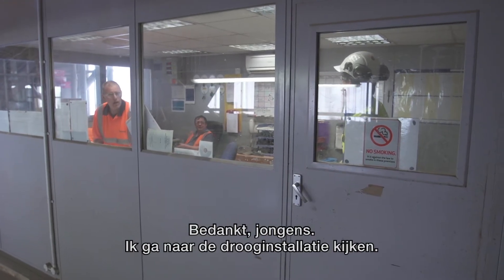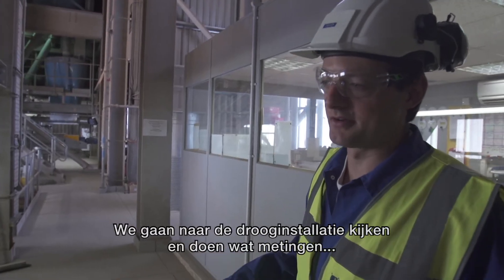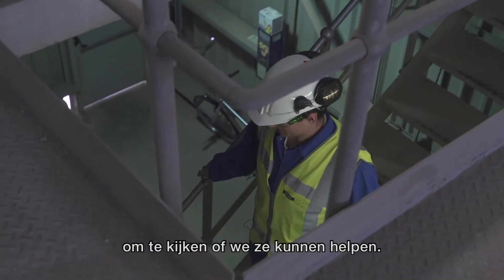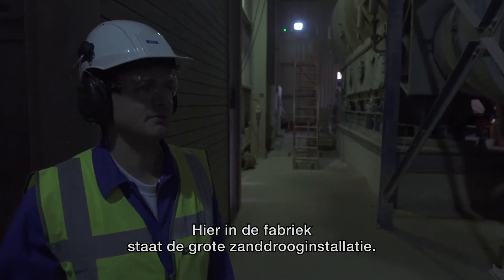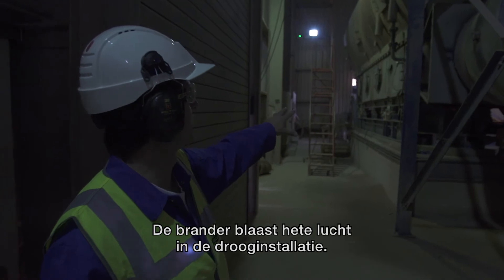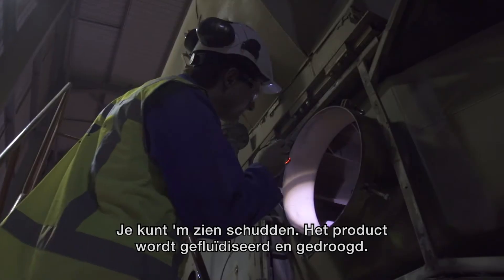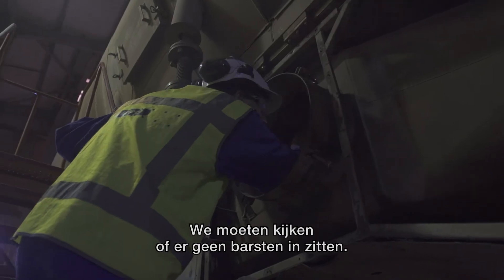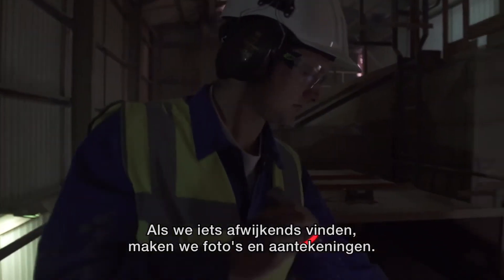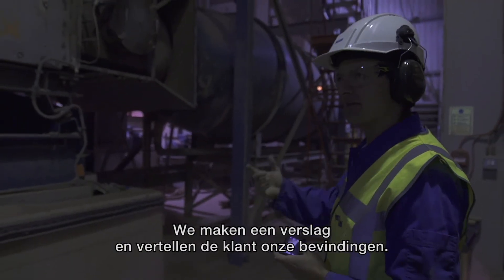I'll go to the dryer. We're going to go down to the dryer, have a look around, walk around some of the equipment, take some measurements, and see if we can help them out with some of the questions they have. Now we're in the factory. Here by the customer is the big sand dryer. We have the burner — it's creating hot air to go into our dryer. As you can see it's shaking, it's fluidizing the product and mixing the product with the air to dry it. We're going to check inside as well, make sure mechanically everything's okay. We want to make sure there's no cracks or anything forming. Anything we find that's different or out of the ordinary, we take photos of it as well as making notes, so we can put it into a report and tell the customer what we found.